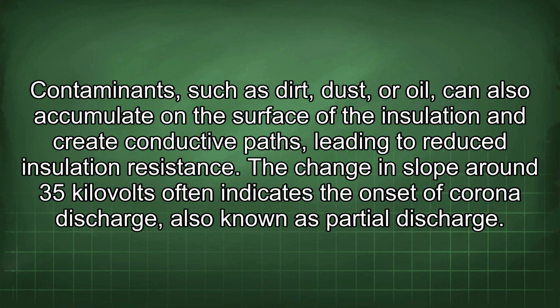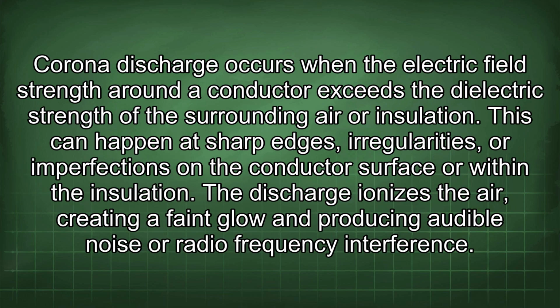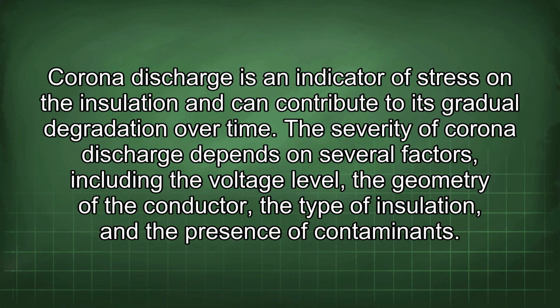The change in slope around 35 kV often indicates the onset of corona discharge, also known as partial discharge. Corona discharge occurs when the electric field strength around a conductor exceeds the dielectric strength of the surrounding air or insulation. This can happen at sharp edges, irregularities, or imperfections on the conductor surface or within the insulation. The discharge ionizes the air, creating a faint glow and producing audible noise or radio frequency interference. Corona discharge is an indicator of stress on the insulation and can contribute to its gradual degradation over time.